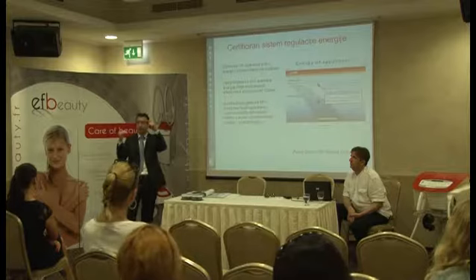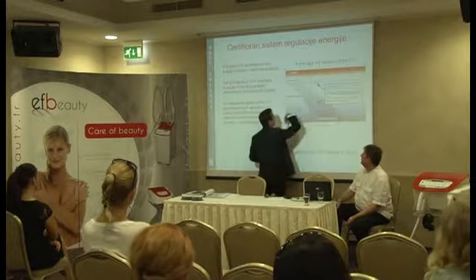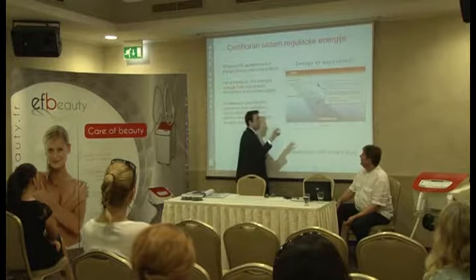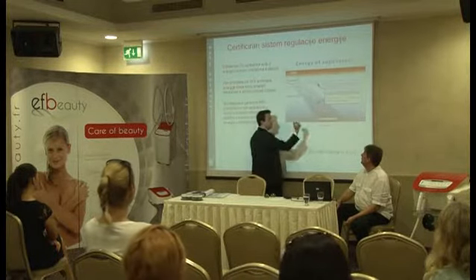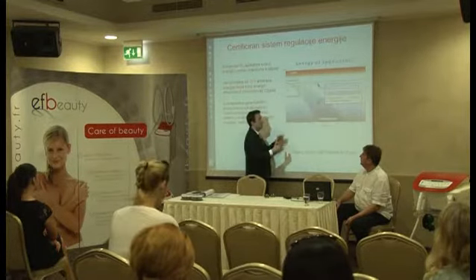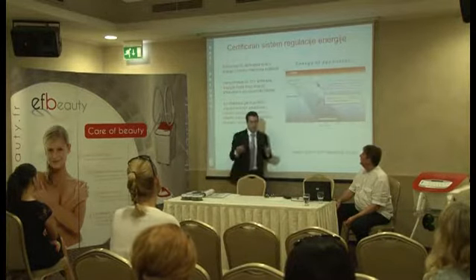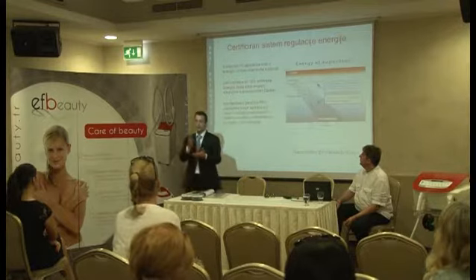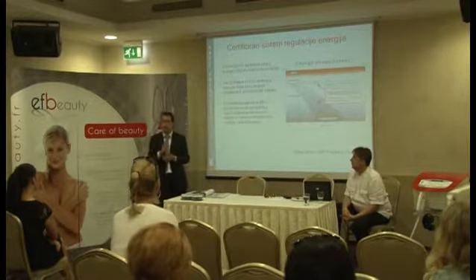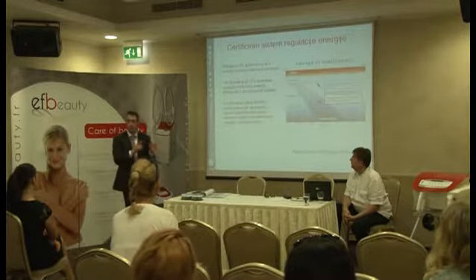So this is the loss of energy, the intensity, of a classic applicator. What we have implemented, because we have an electronic card so we can manage this, is that our generator will compensate for the loss of energy. It will send a little bit more energy in order for the applicator to always deliver what you ask. If you ask for 16 joules, it will give you 16 joules, and this is guaranteed. We guarantee that from the first to the last flash, you will have the same amount of energy.